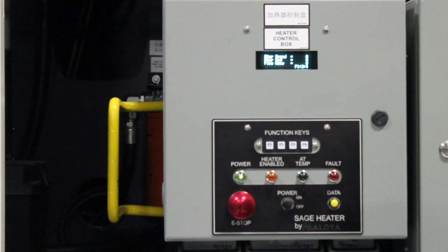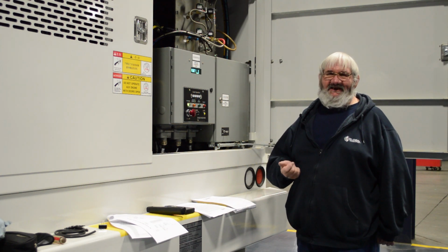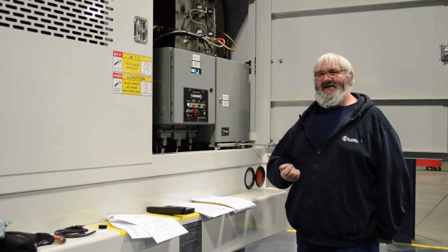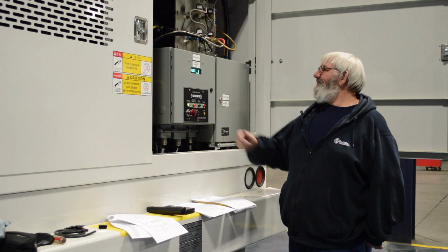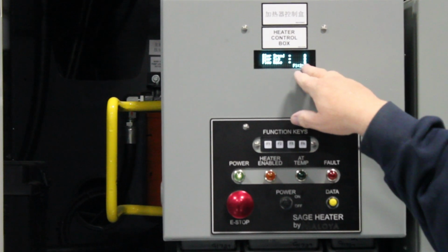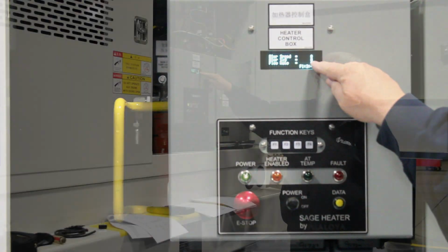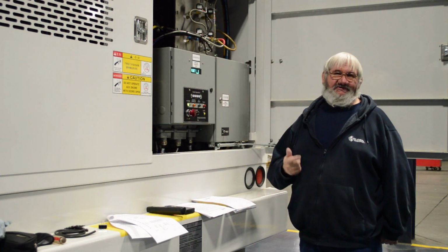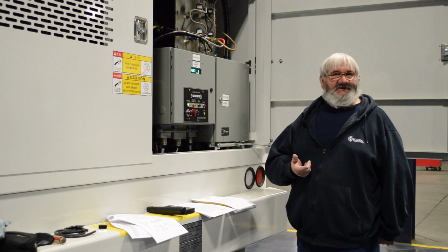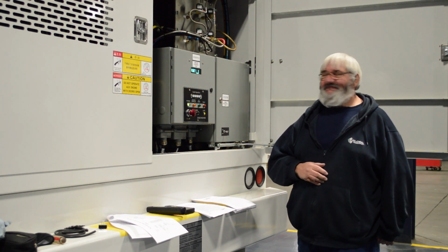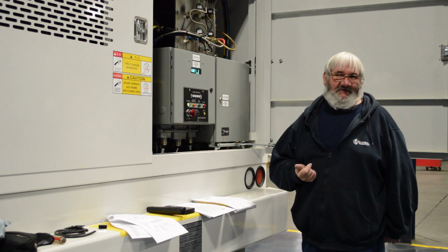Your blower speed. This is your blower stage. And the stages 1 through 13 are your heating stages. Stage 14 is your light off. Stage 15 and 16 are your post-purge stages. And then your flow rate. This is where you would see what your flow rate is through the heater and your blower signal. Now remember, your blower signal varies between 0 and 4095. 0 signal should give you 300 to 500 RPMs. 4095 signal should give you 5,000 RPMs on your blower.